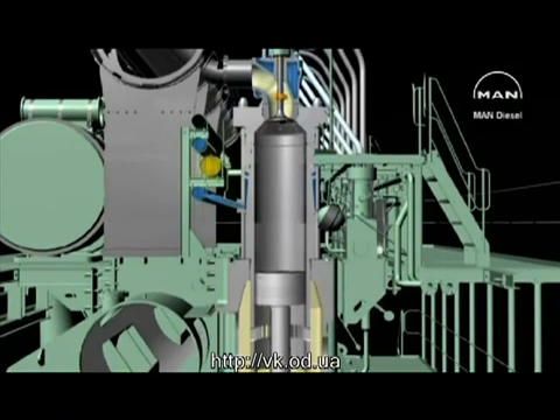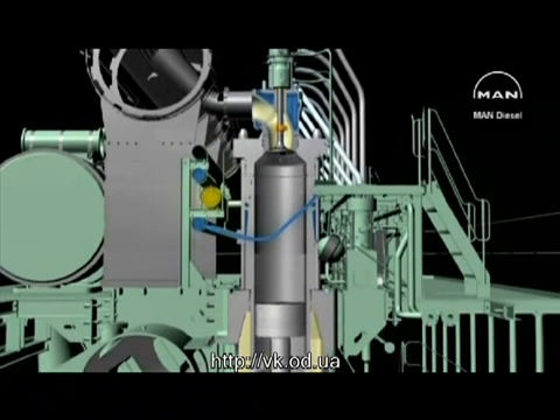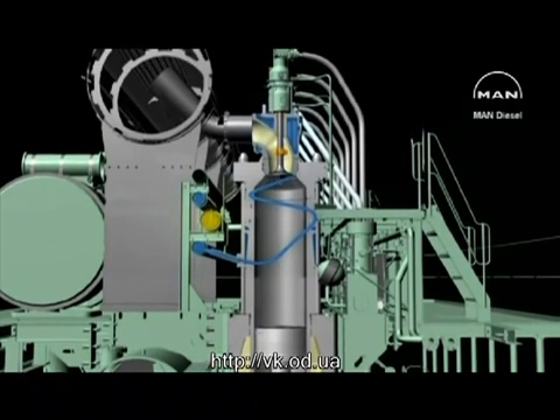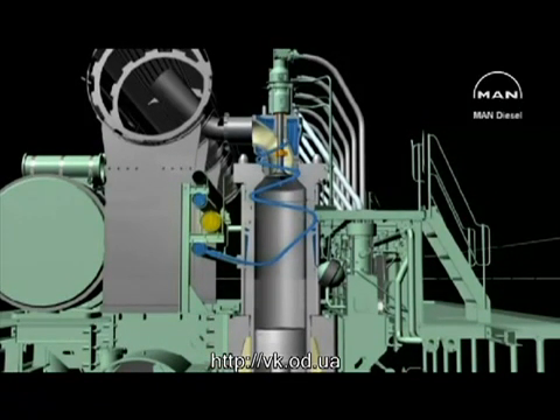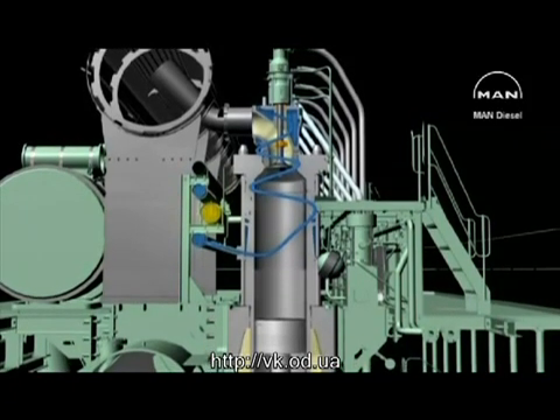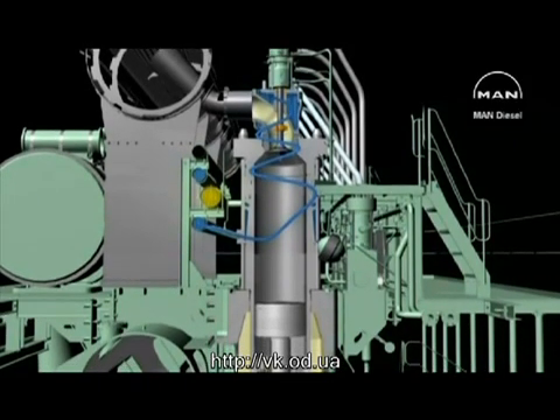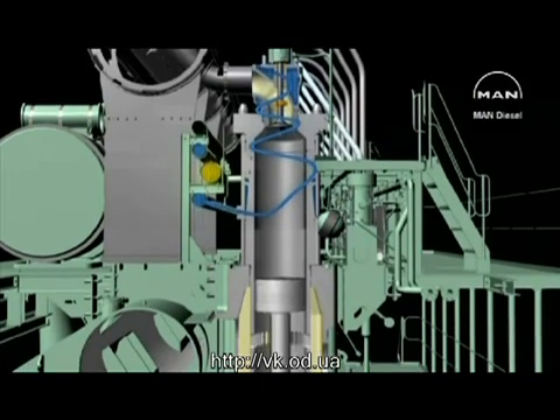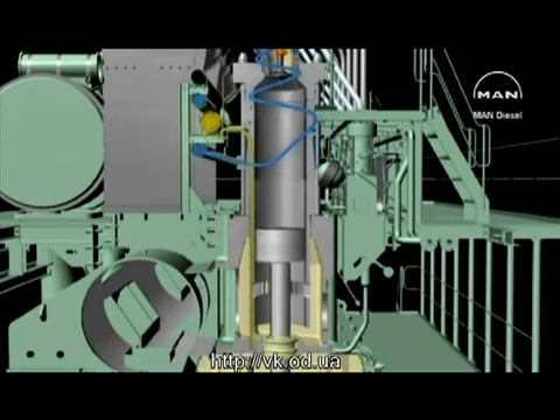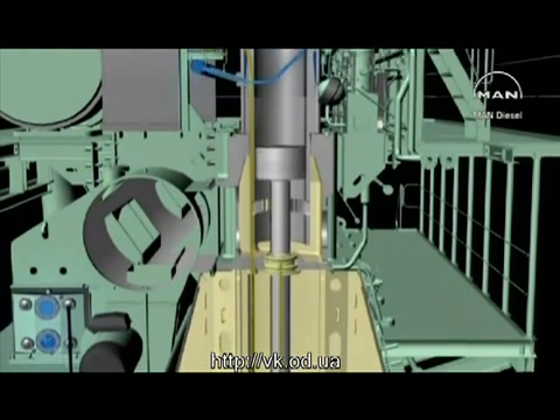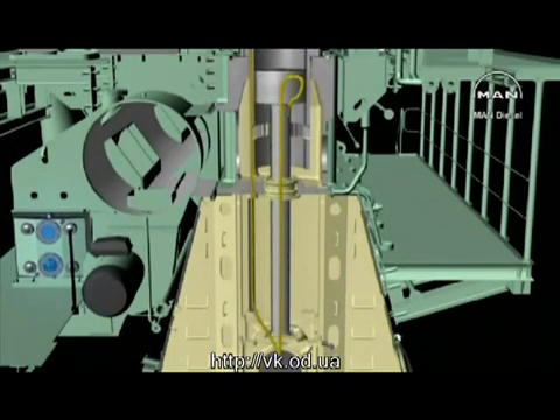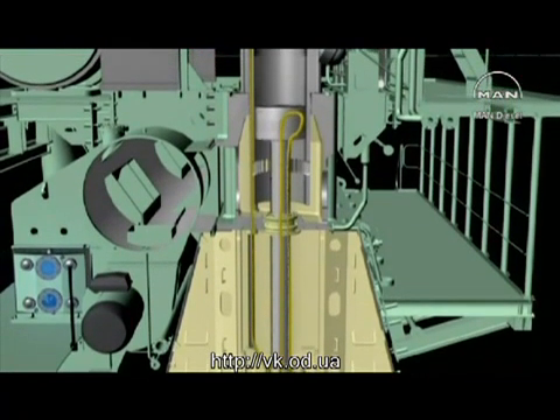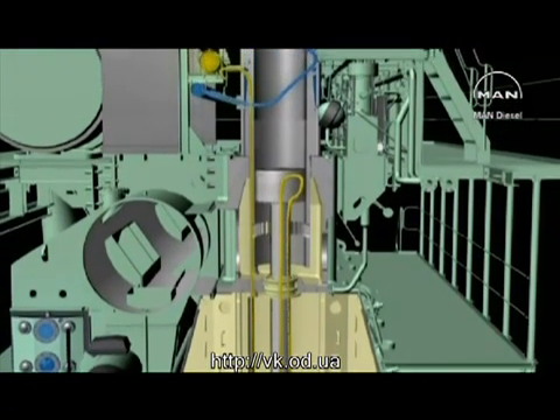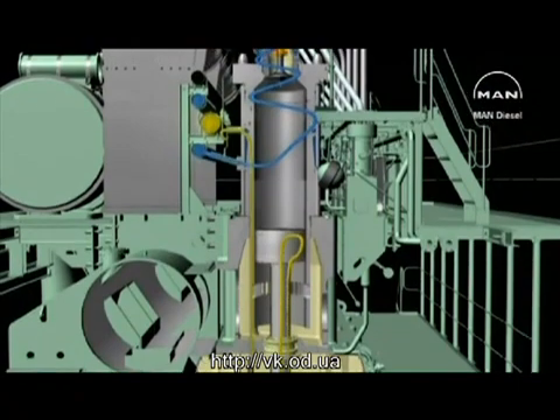It's therefore necessary to provide efficient cooling, partly with oil led through the piston rod up into the piston itself, and partly with water circulating through the cooling jacket around the cylinder and cylinder head, and passing rows of narrow drill channels placed close to the most heavy, heat-loaded internal surfaces. If a cooling water outlet temperature of about 80 degrees centigrade is maintained, we can prevent the temperature on the inside of the cylinder wall from exceeding 300 degrees centigrade. This is possible because there's a drop in temperature as the heat passes from cylinder gas to metal.